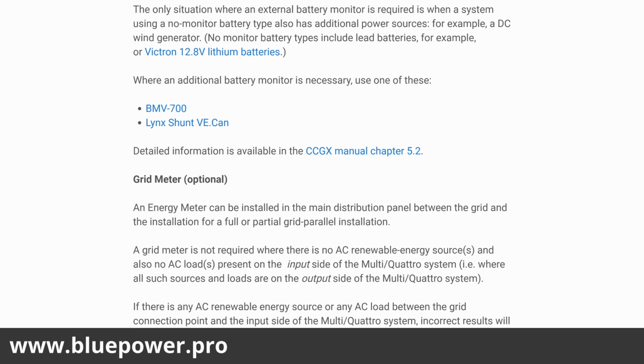The battery monitors can also now be set up as an energy meter or DC energy meter. So if you have one or multiple sources of energy, DC charging sources that aren't compatible with the Victron system, you can still monitor their power accurately via a BMV. Just set it up as an energy meter instead of a battery monitor. That can be either the Lynx Shunt VE.Can or the normal BMV 700 range.